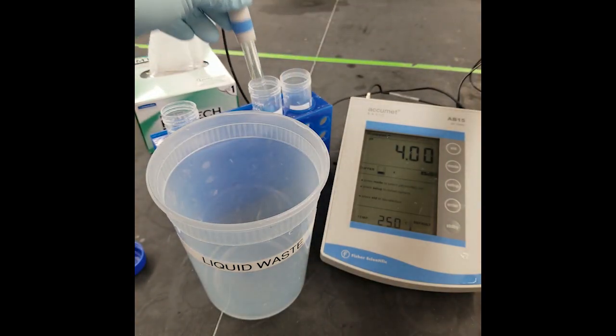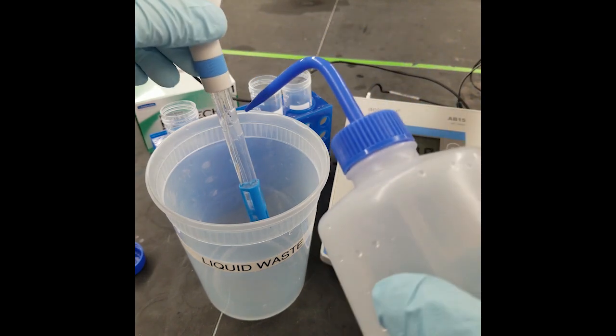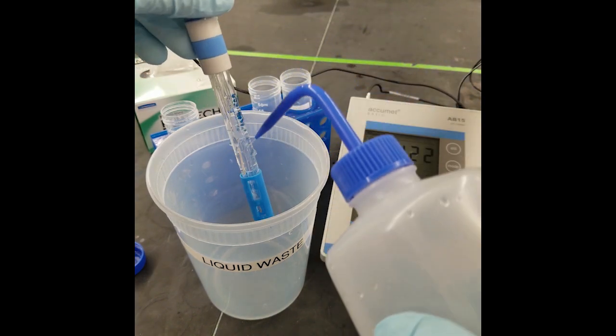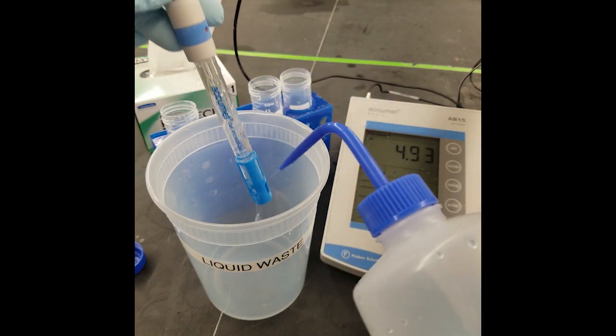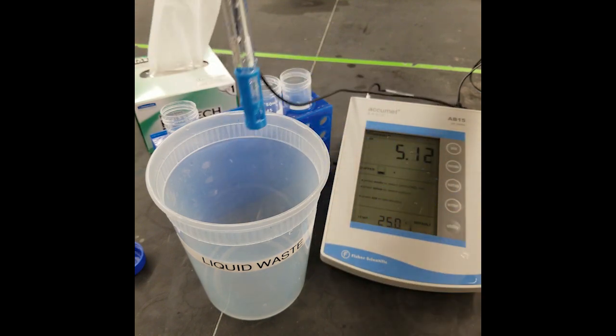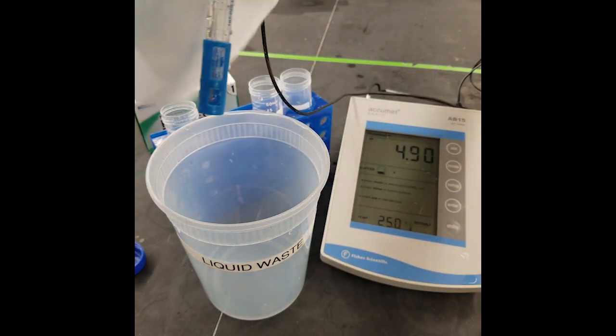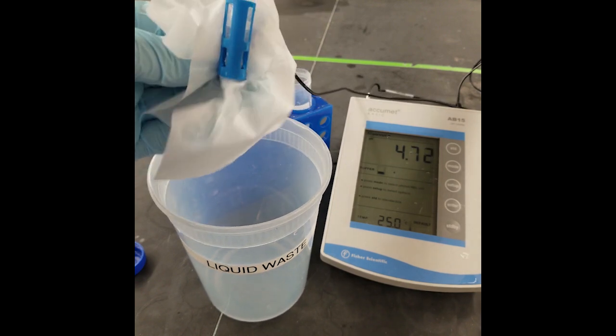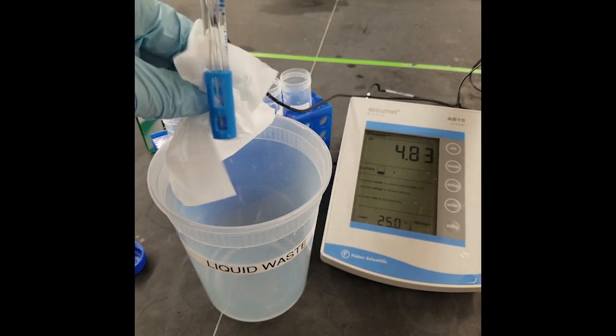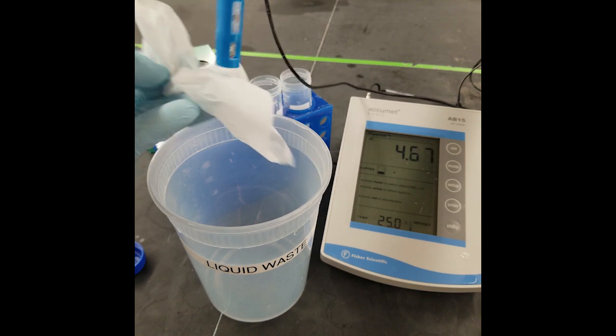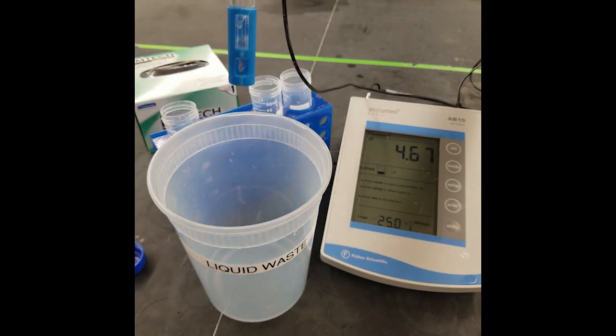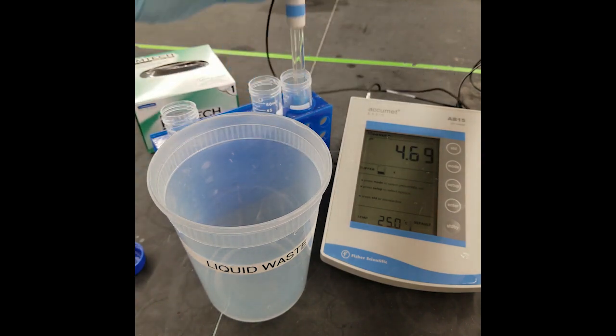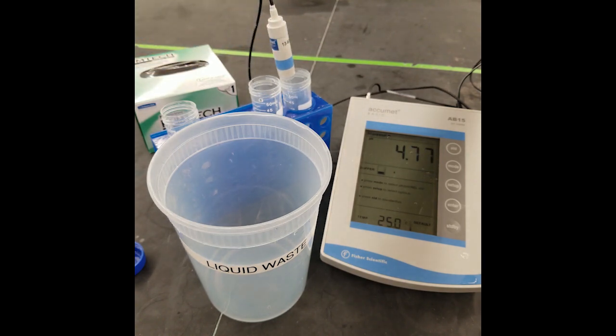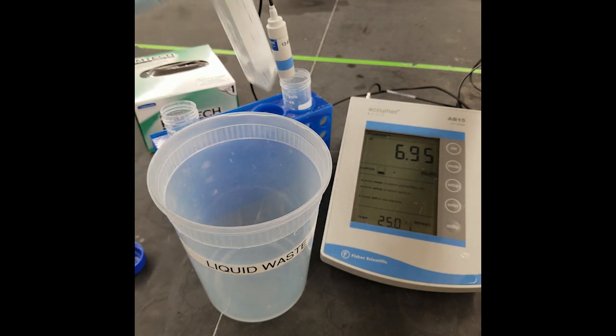So we're going to take our pH meter out of the pH 4 solution, rinse it with some DI water over our liquid waste container, shake off any excess DI water, blot the DI water, or I should say blot your pH probe, dry using a Kim wipe, and then go ahead and insert your pH probe into the conical tube containing the pH 7 standardization solution.